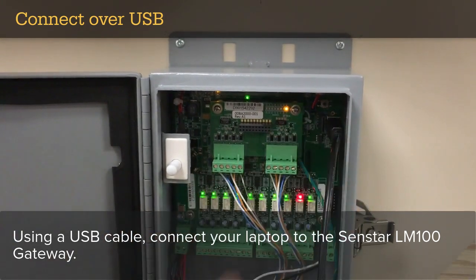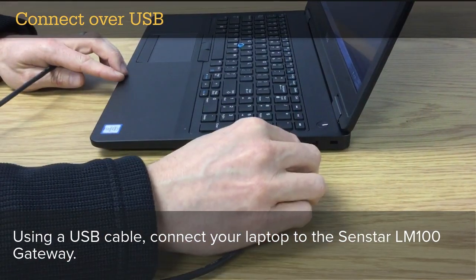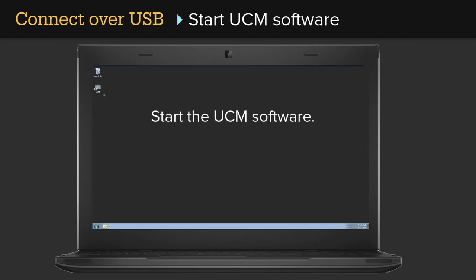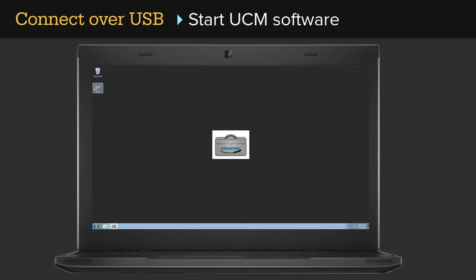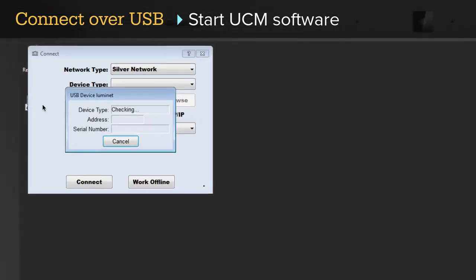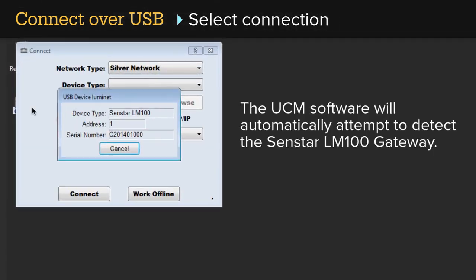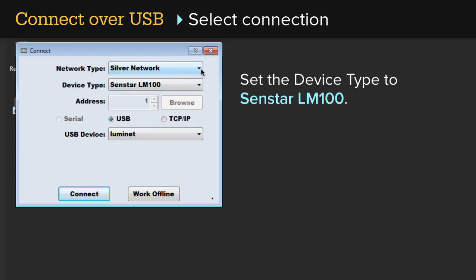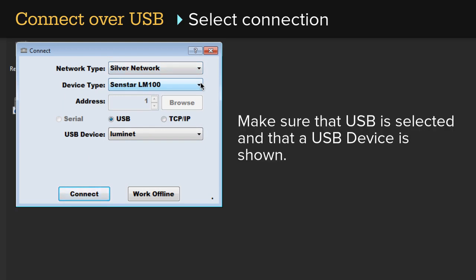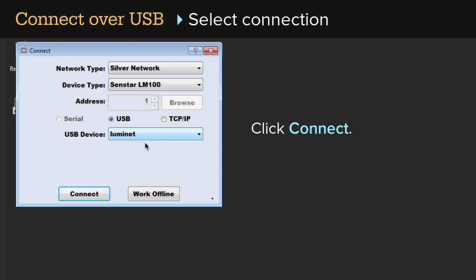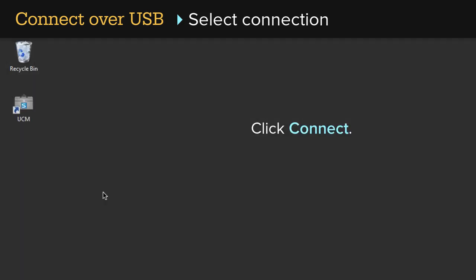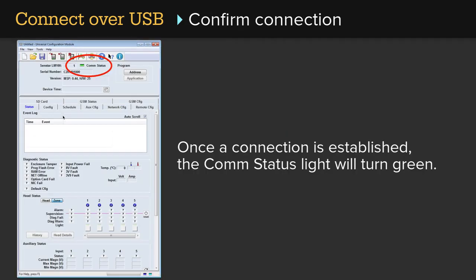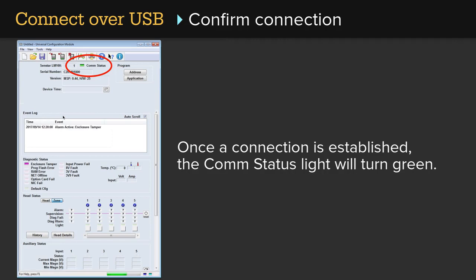Using a USB cable, connect your laptop to the Senstar LM100 gateway. Start the UCM software. The UCM software will automatically attempt to detect the Senstar LM100 gateway. Set the network type to Silver Network. Set the device type to Senstar LM100. Make sure that USB is selected and that a USB device is shown. Click Connect. Once a connection is established, the COM status light will turn green.